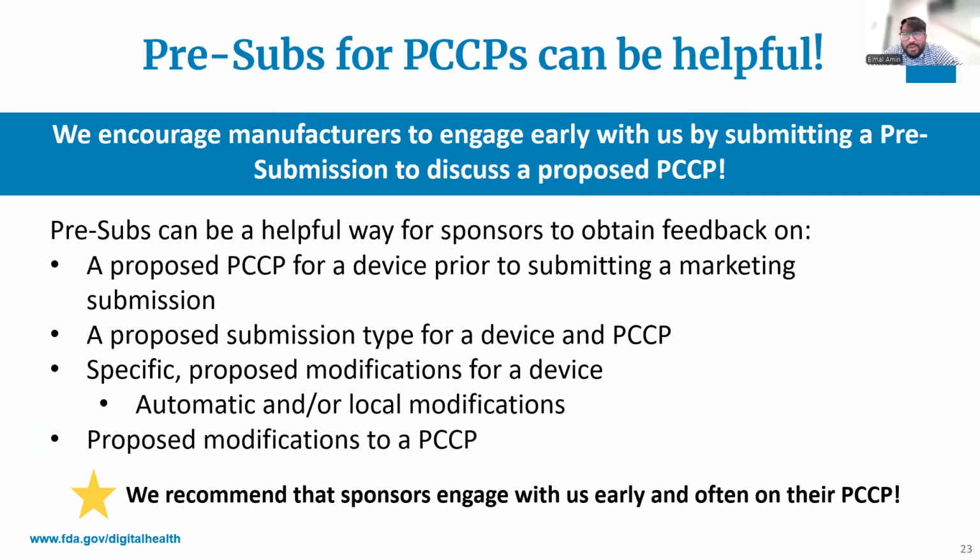We understand that predetermined change control plans are relatively new, and you may have questions regarding them. We recommend that manufacturers engage with us early by submitting a pre-submission to discuss their PCCP, where you can obtain feedback on questions related to the proposed modifications, the modification protocol, and the impact assessment. A pre-sub is a way to get FDA feedback on your PCCP before you file your pre-market submission.